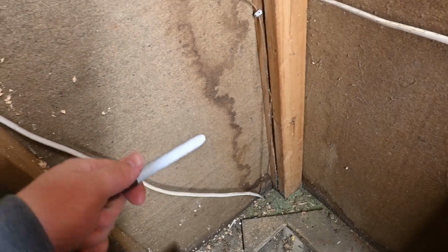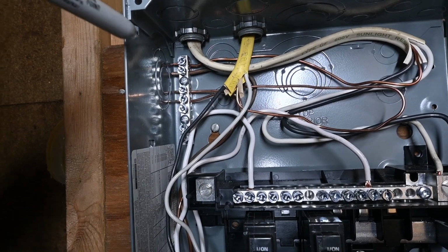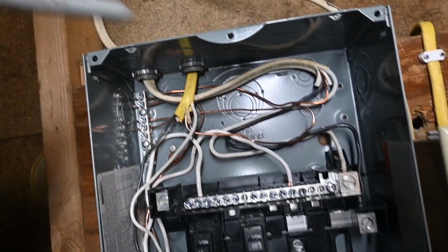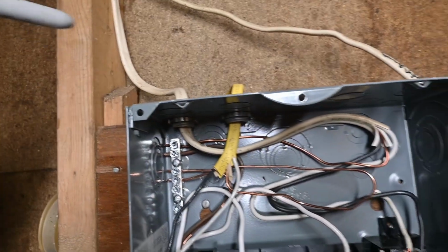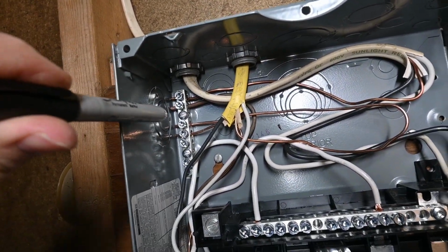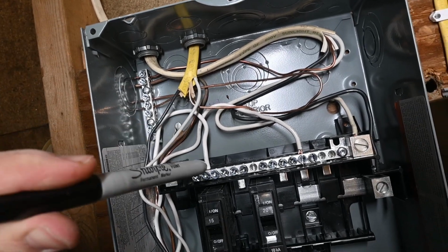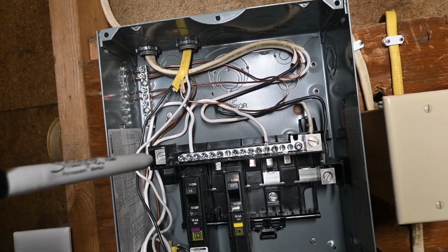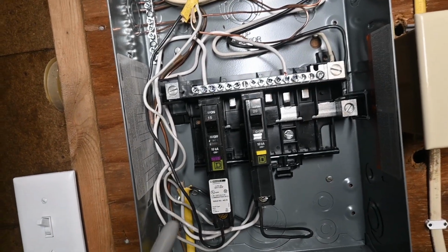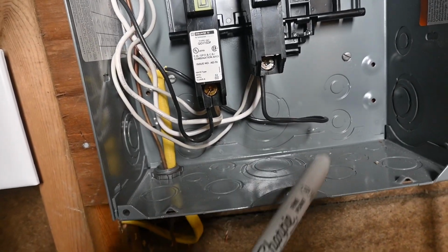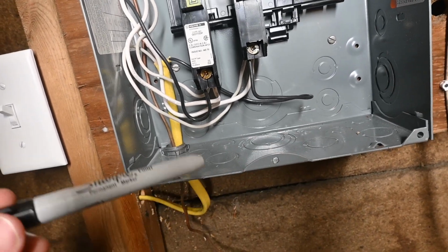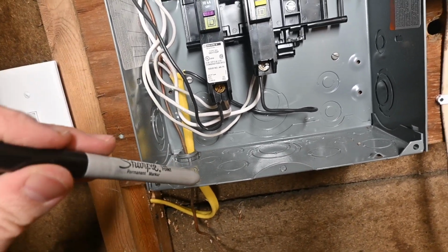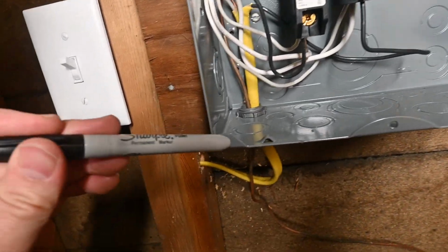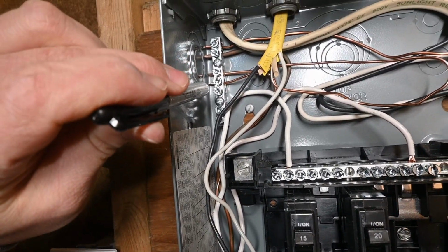First of all, we do have a grounding electrode conductor coming up and connecting to our ground bar in the back of the panel, just like it's supposed to. Our ground wire from our circuit that's supplying this box is also properly connected to the ground bar. The ground bar is separated from the neutral bar, which is something that you're supposed to do with sub panels. So if there were to be a dead short from, say, one of these black wires here to the frame of this panel, it would trip using the effective ground fault current path, which is going through the frame of this panel to that ground bar and then onto the ground wire that makes its way back ultimately to the main panel.